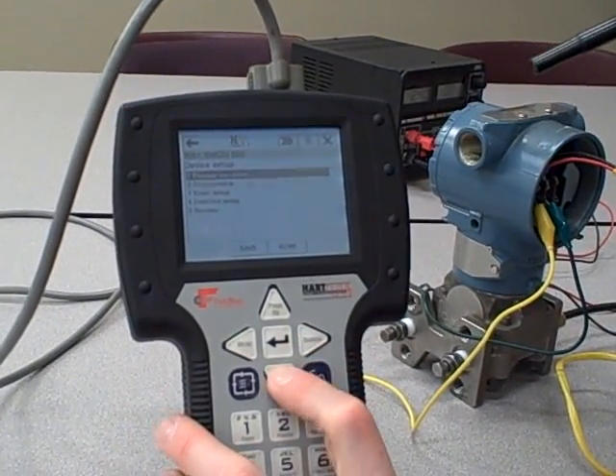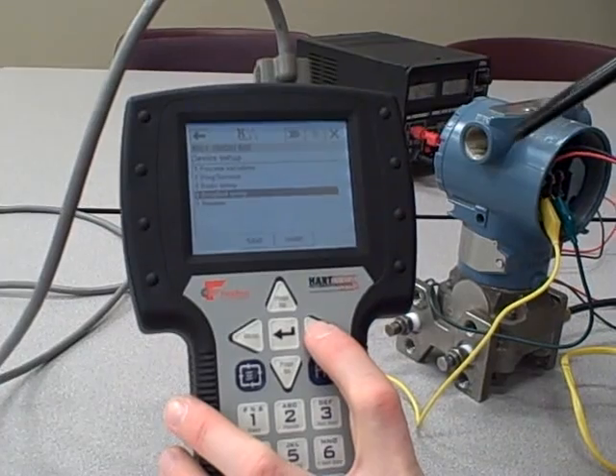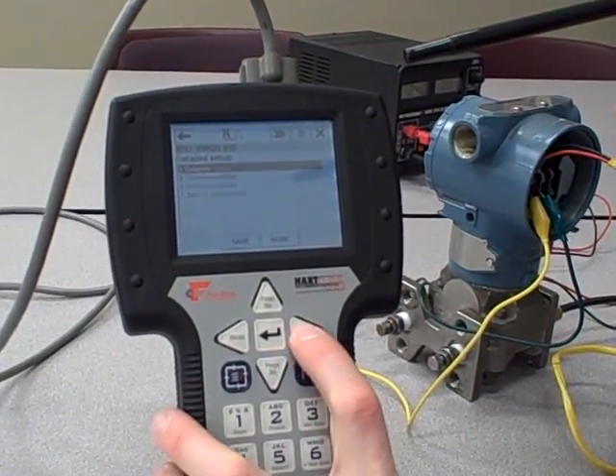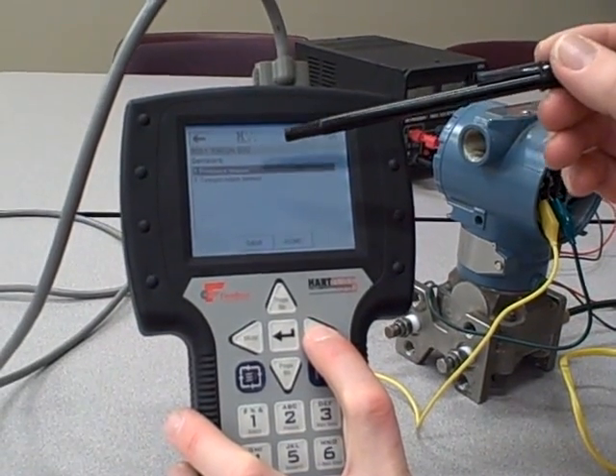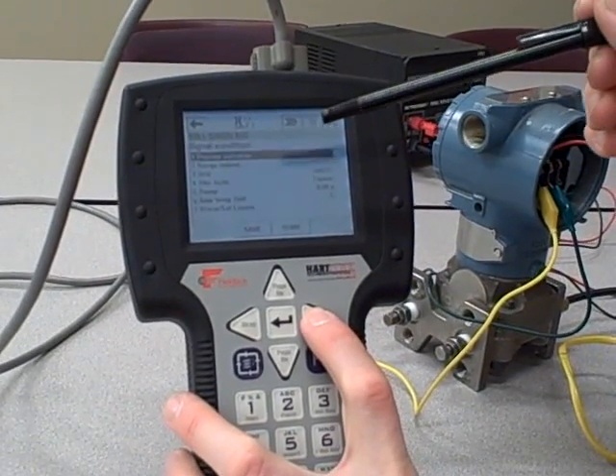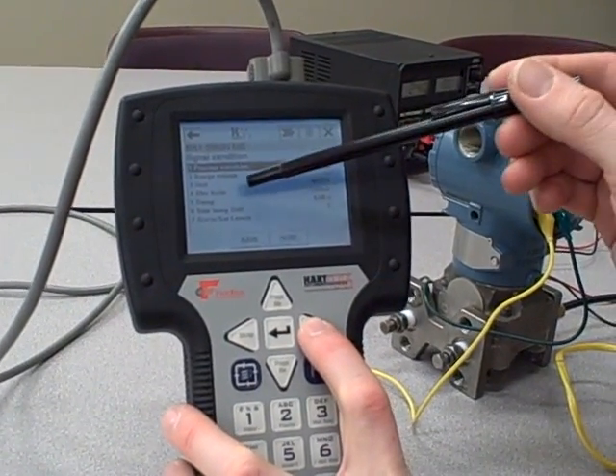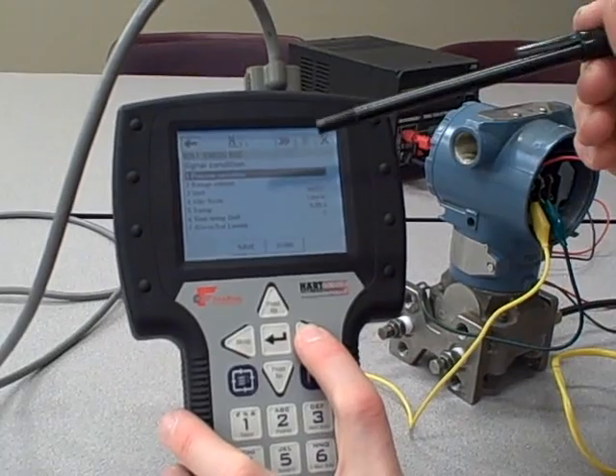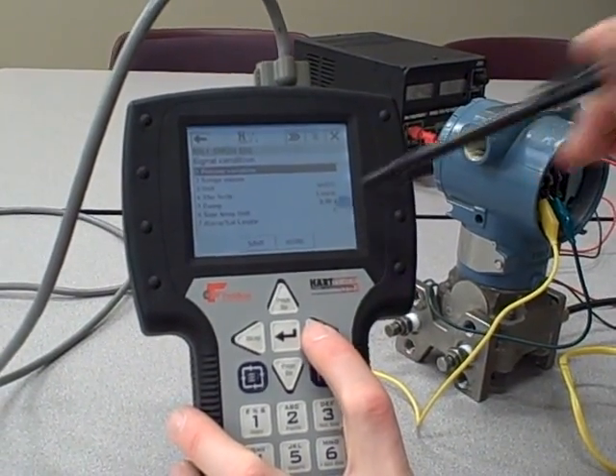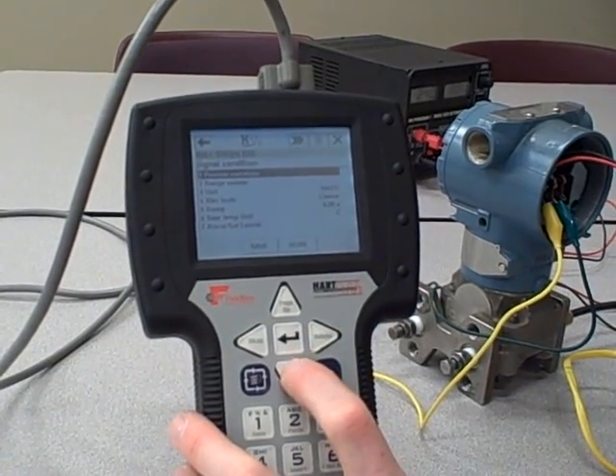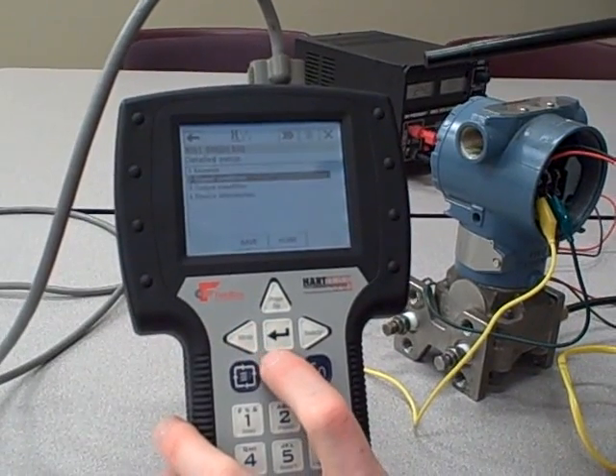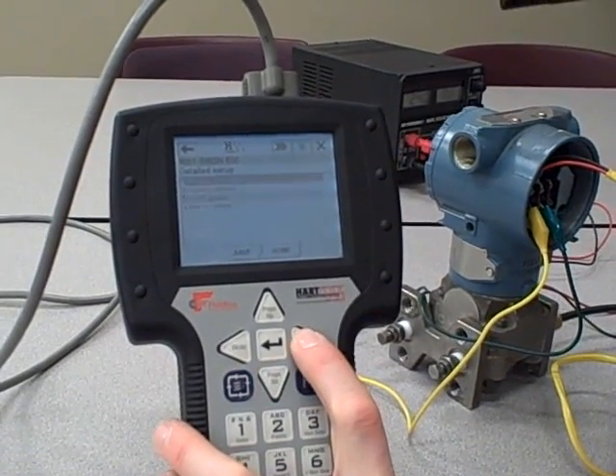Going back to the Device Setup menu, we also have Detailed Setup, in case Basic Setup wasn't detailed enough. We can go into Sensors, in which case we can configure things regarding the pressure and temperature sensor. Signal Conditioning - once again, this is a transfer function, linear versus square root. Sensor Temperature Unit, that's the ambient temperature sensing unit in the transmitter. We can set that for degrees Celsius or Fahrenheit. Alarm Saturation Levels, Damping, Range Values, etc.